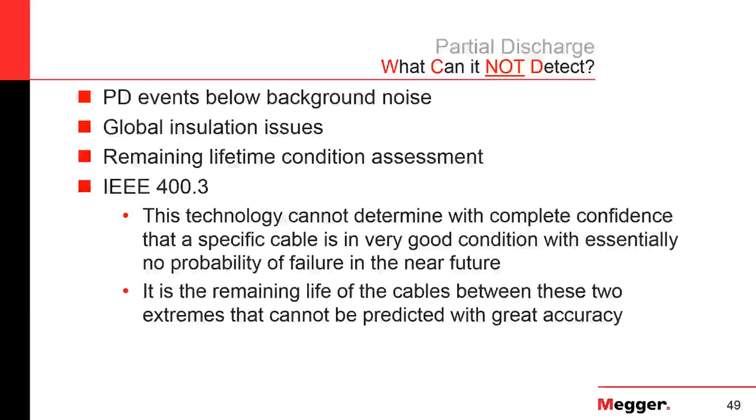It's difficult to give a remaining condition, remaining lifetime assessment with partial discharge. There's certain red flags that we can say, but it's very difficult to say this cable is going to be good for the next year or 6 months or something. It's more of a threshold: this cable is in good shape or this cable is in bad shape.